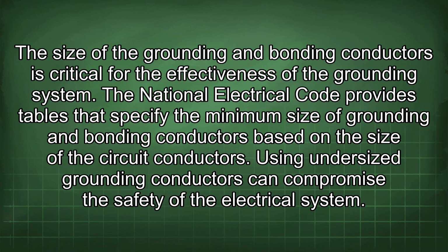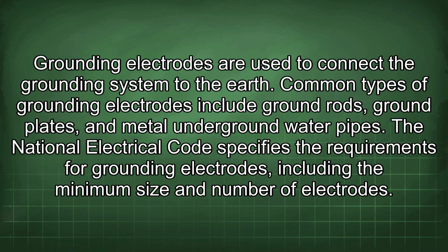The National Electrical Code provides tables that specify the minimum size of grounding and bonding conductors based on the size of the circuit conductors. Using undersized grounding conductors can compromise the safety of the electrical system. Grounding electrodes are used to connect the grounding system to the earth. Common types of grounding electrodes include ground rods, ground plates, and metal underground water pipes. The National Electrical Code specifies the requirements for grounding electrodes, including the minimum size and number of electrodes.